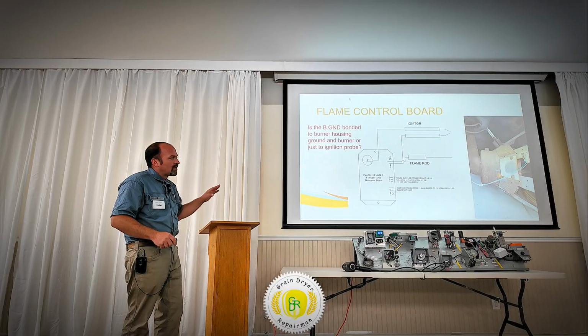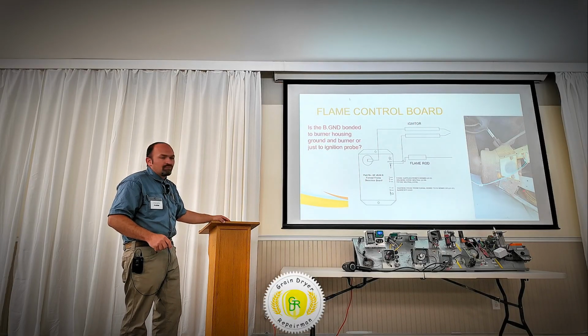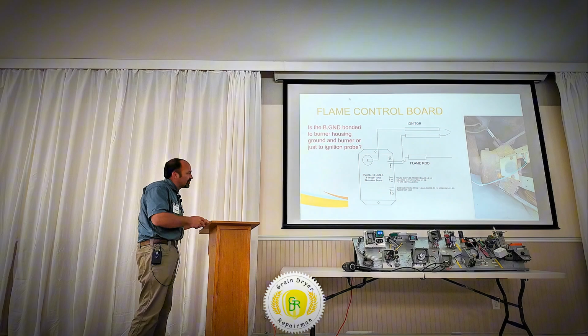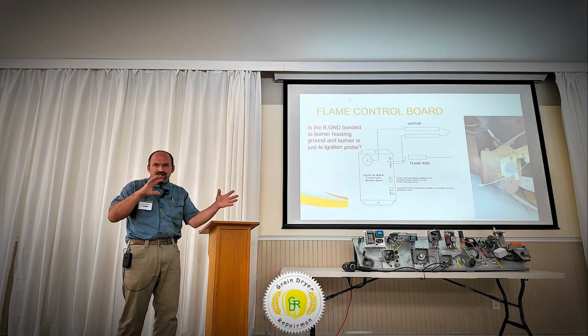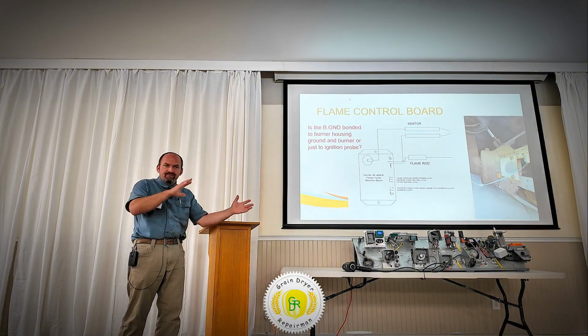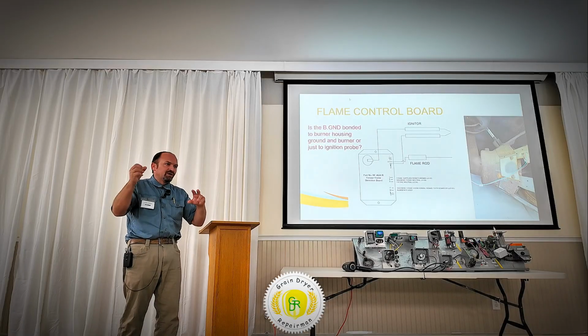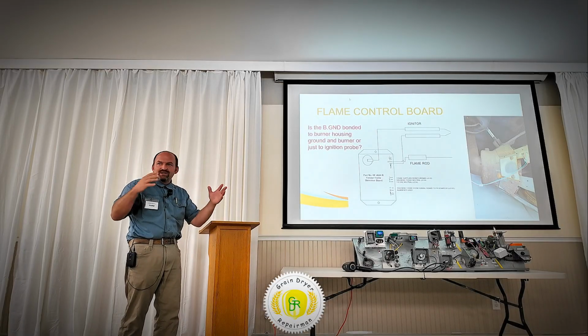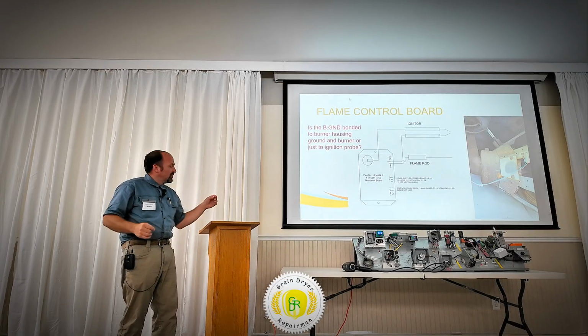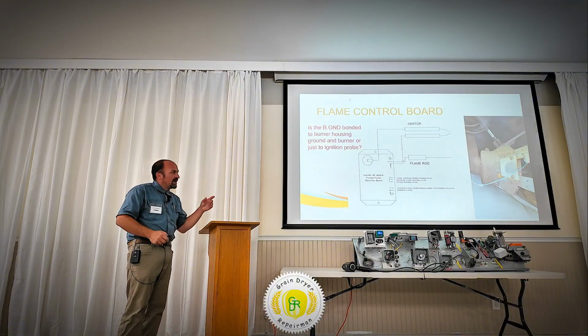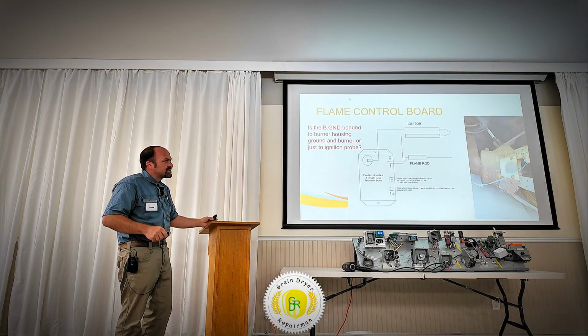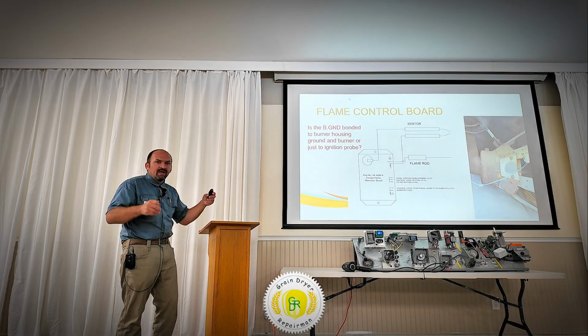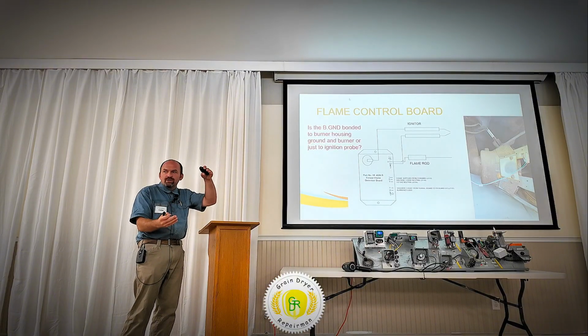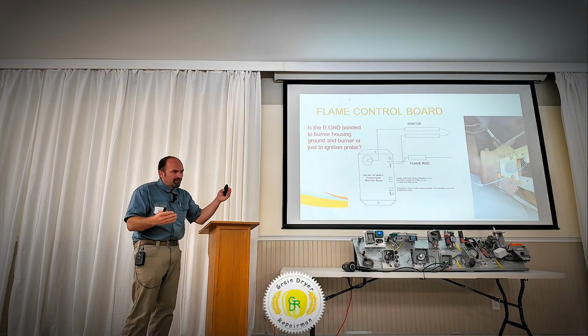On the Starfire burner, you want to add a second flame rod, because in these burners the flame kind of moves around in there, and it can leave the flame rod and come back against the flame rod. You can move it, but you're kind of chasing the wind. So you're best off putting a second flame rod in. It does not need to be on the other side. You can have one flame rod here and one on this fin down here, or even on this fin. They don't usually have to be far apart to really improve your flame sensing.